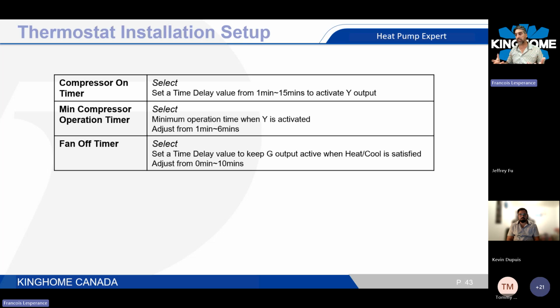Fan off timer is a time delay value to keep the G active whenever the heat or cool demand is off. You can adjust it from 0 to 10 minutes, meaning whenever your gas furnace or your heat pump is in heat mode and you want to blow some air after the heating process, just to make sure you cool down the coil or the combustion chamber as well, you can run the fan maybe a minute and a half after the heat call has ended.